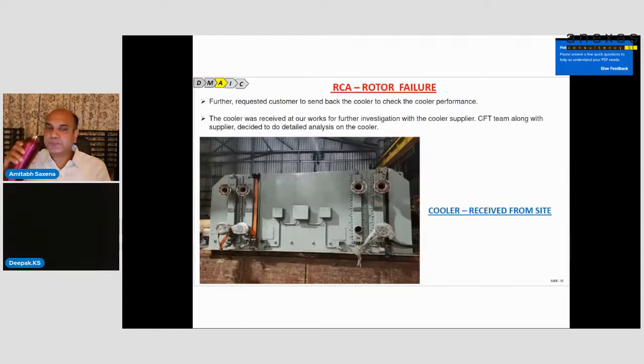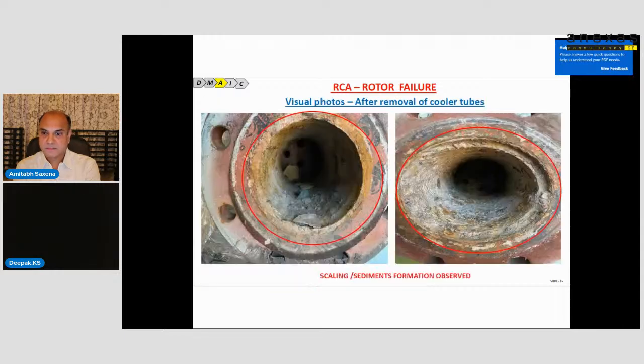Yes, further we requested the customer to send back the cooler to check the cooler performance. This is the cooler which our supplier has supplied, which mounts above the generator because it's a top side cooler to cool the machine. This is the photograph of the cooler we received from the site. Next. Yes, we removed the cooler tubes. We can see some visual photos of the cooler tubes where scaling and sediment formation are observed when we remove the cooler tubes. Next.